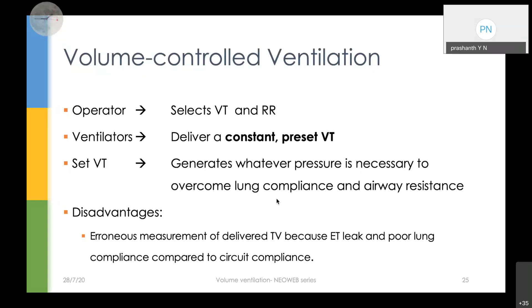So when the ventilator is working mechanically, we know that problems could arise, correct? Because we said that the tidal volume being measured is at the ventilator end, in expiration, where we don't know what is happening at the baby's end. We just know that the volume of air is going and we are checking it. So it gives an erroneous measurement of delivered tidal volumes because it doesn't look into the ET leak. If there is any ET leak, it doesn't take it into account. It doesn't take into account the poor lung compliance, and also doesn't take into account the circuit compliance. We'll come to it with the figure over here.